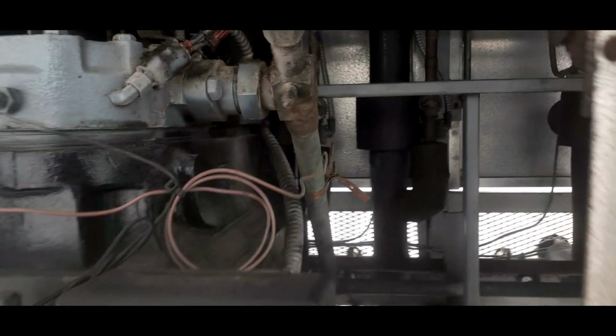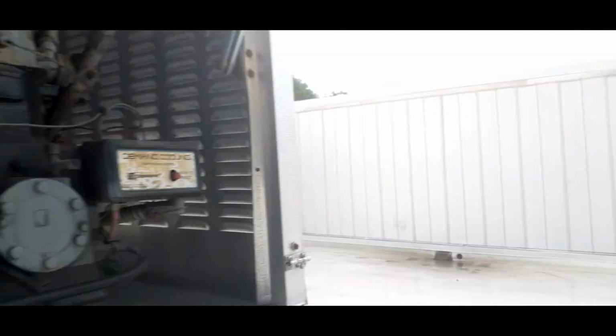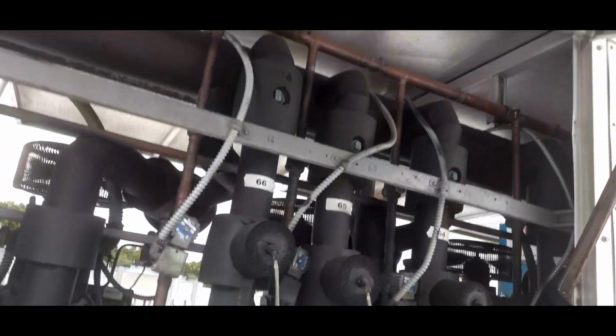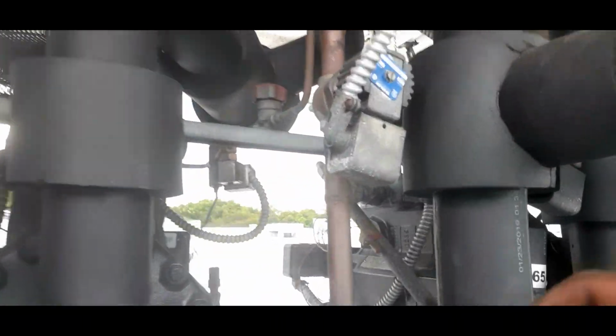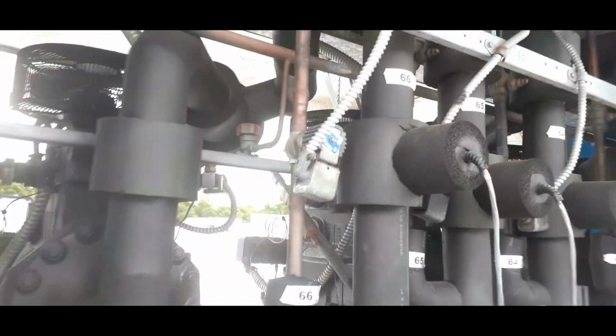That's one. That's one. We would have a hot gas solenoid open up, knock these compressors off on overload. What could it be? I don't know if you can hear this, but this one here sounds like it's a problem. Let me see if I can turn the compressor down so we can pick up on that sound. That solenoid is sticking, I guarantee you.